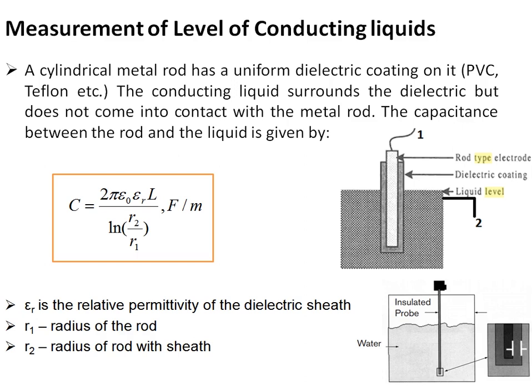For conducting liquids, a rod-type electrode is used with a dielectric coating surrounding it, acting as an insulator. Here the dielectric constant throughout the electrode is constant and does not change. What changes is the overlapping length L of the concentric cylinder formed by the conducting liquid around the dielectric coating. As the liquid level rises, the overlapping length L increases, which directly affects the capacitance.